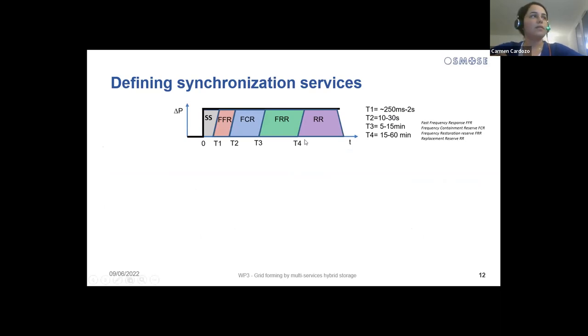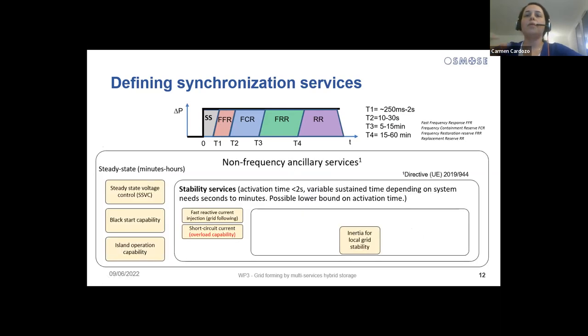this is synchronizing services, between zero and T1, and T1 can be rather 250 milliseconds, 2 seconds, depending on the system and when we start to define new ancillary services like fast frequency response or things like that.